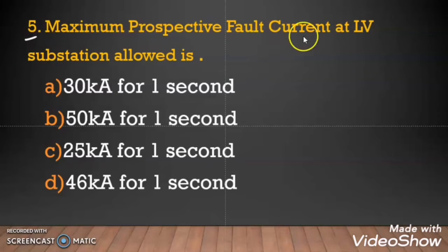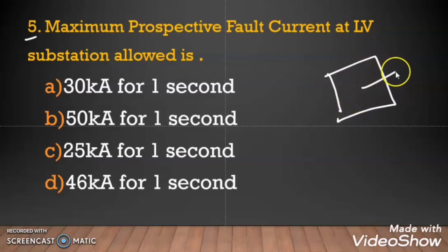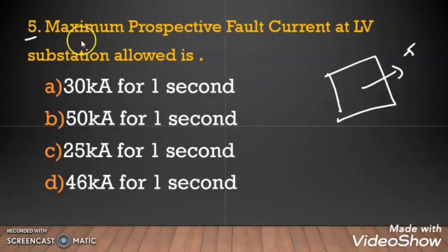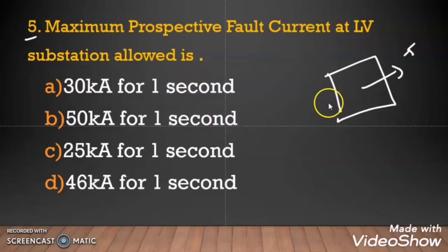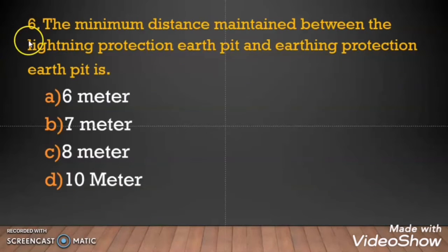Question 5: Maximum prospective fault current at LV substation allowed. The prospective short circuit fault current depends on your transformer rating. The answer as per ADDC regulation is 46 kilo ampere for 1 second. That is the maximum prospective fault current allowed at the LV substation level.